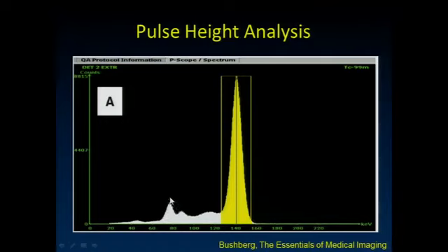What's that peak from? Yeah, that's scatter within the collimator. That happens to correspond to the characteristic X-ray energies of lead, and our collimator is made of lead. So when events interact in the lead collimator and we get some characteristic X-ray production, we certainly don't want to include those in making our image.